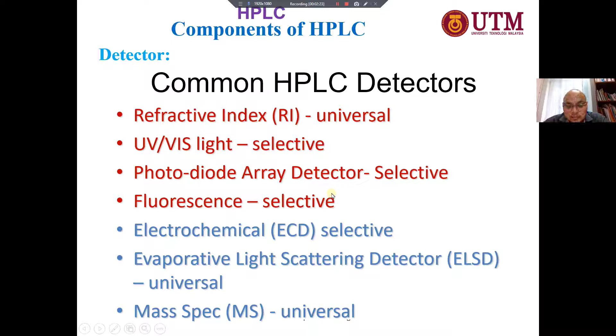Here is the refractive index detector, the first detector we will learn. Here is the incident beam. Here is the sample cell, and here is the reference cell. That's why the mobile phase refractive index must be different compared to the sample. For example, in the reference cell is our mobile phase. If the sample and the mobile phase in the reference cell have the same refractive index, the incident beam will not be deflected. So nothing changes and the incident beam reaches the detector. That happens if the RI is the same between the sample and the mobile phase.